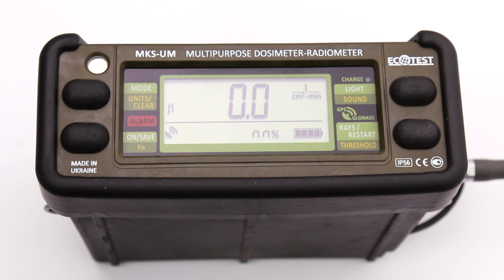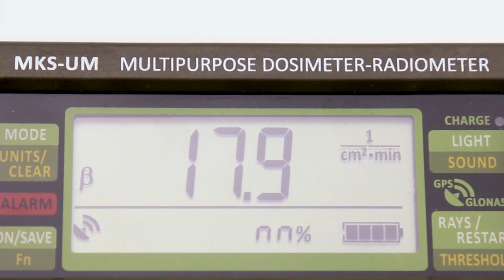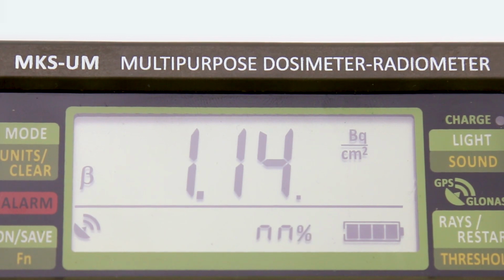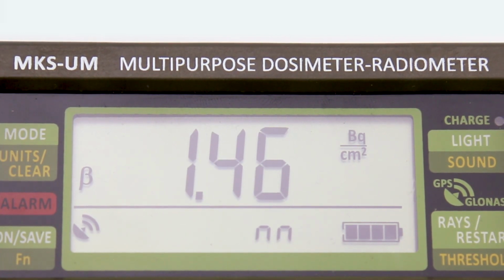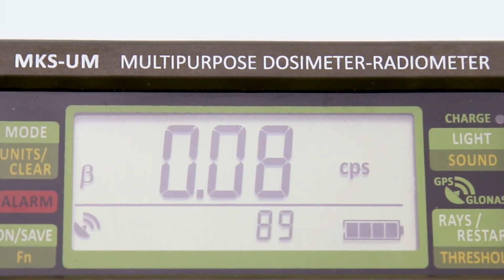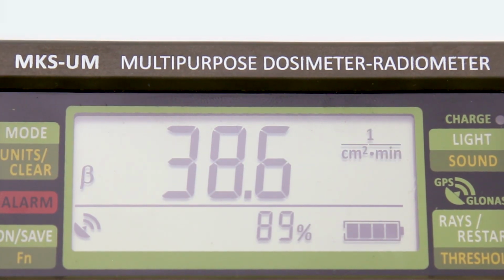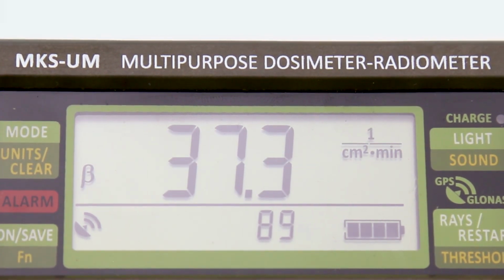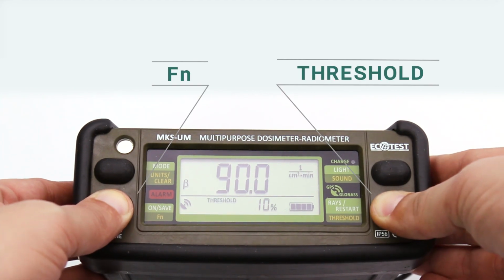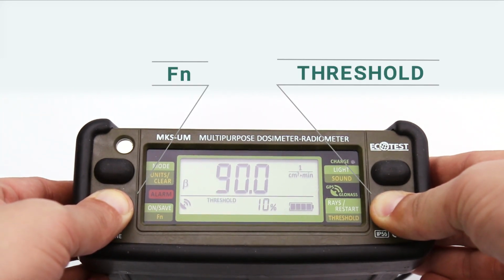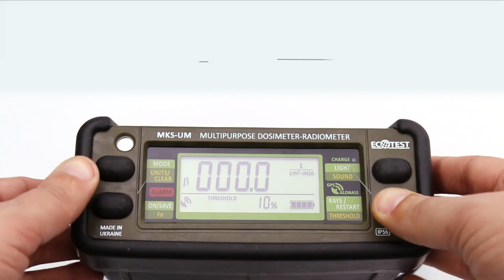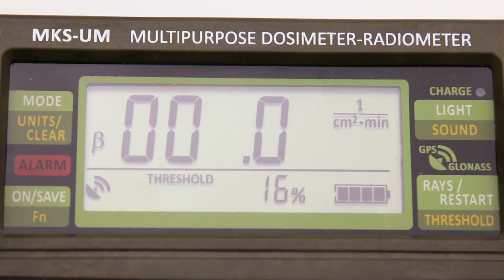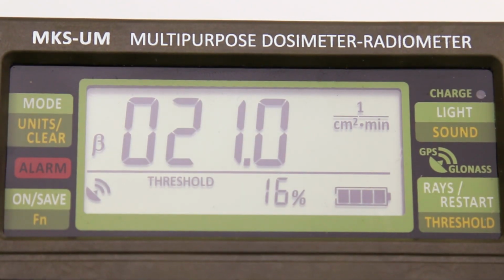When the threshold level of the beta radiation is exceeded, the sound and light alarms are activated. When measuring the beta radiation, the device operates with 3 independent threshold levels. You can set different threshold values for different measurement units. You can view and set the threshold level and program statistical error for beta radiation in the same way as for the dose rate of the photon ionizing radiation.